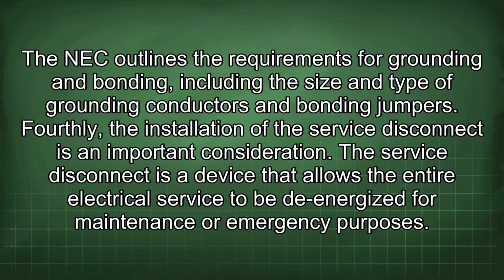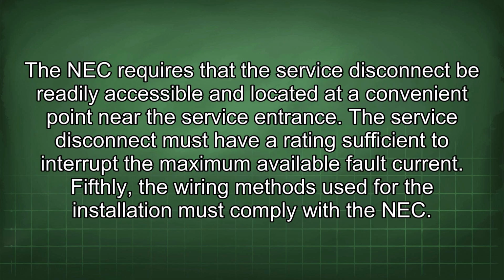The service disconnect is a device that allows the entire electrical service to be de-energized for maintenance or emergency purposes. The NEC requires that the service disconnect be readily accessible and located at a convenient point near the service entrance. The service disconnect must have a rating sufficient to interrupt the maximum available fault current.